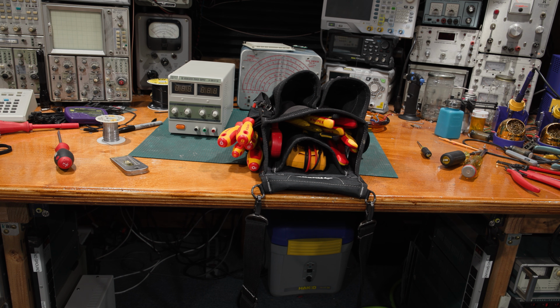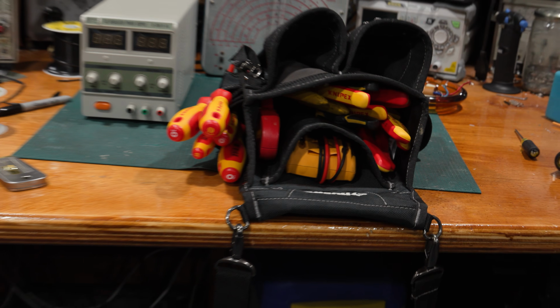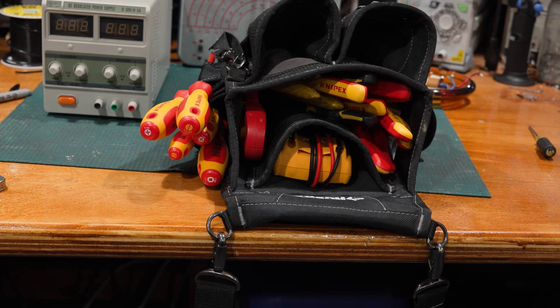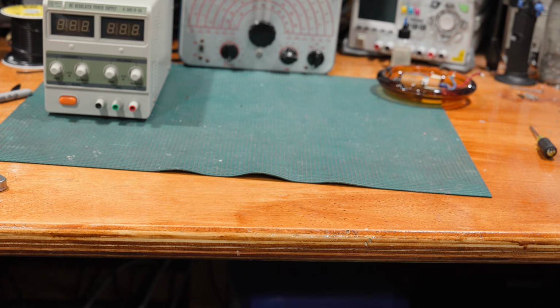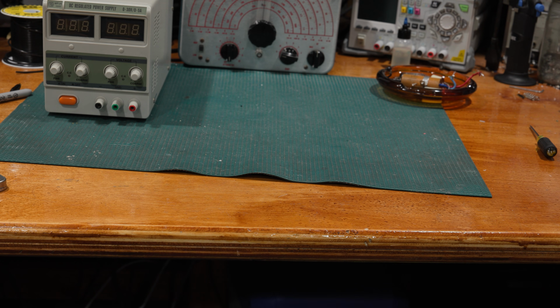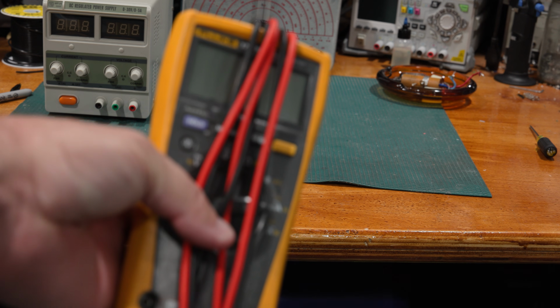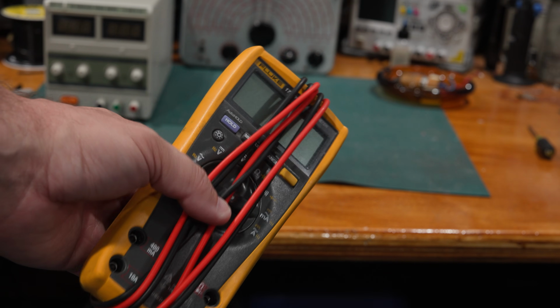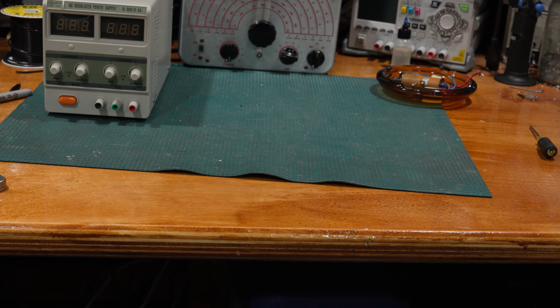So the 7510 is not a metrology level meter. It is a 7.5 digit DMM. It is a very capable meter by every stretch of the imagination. It is not, however, a Fluke calibration DMM or a 3458A, the 8.5 digit HP. Now, I've been into some instrument repair labs that have absolutely had that as their highest reference in the lab, but they worked on stuff like this. So they worked on 3.5 digit DMMs, maybe a couple of 4-digit DMMs. In that case, a 7510 at 7.5 digits is plenty of accuracy to do those alignments and calibrations.